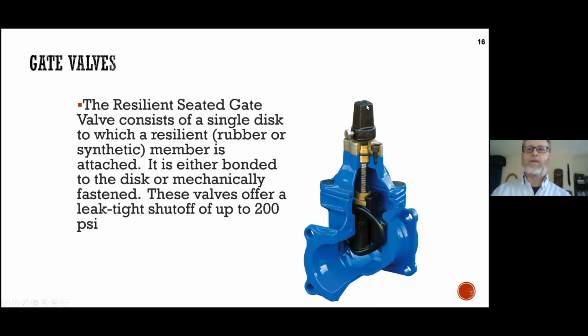So if you allow UK variant, of course, typical with a true UK valve is it's a right hand. Normal AWWA standard is what we would call a left hand thread. So turning clockwise closes the valve, counterclockwise opens the valve. If you're in Britain or in parts of Canada that use the UK system, and maybe you have some of those, it's a 38 millimeter operating nut, and it's right hand, so everything is backwards. So you have to be careful that you're not closing when you think you're opening, and vice versa. There was a city nearby here, and I told you, I had an issue around a fire hydrant that broke and could not close the valve because they were turning them the wrong way.